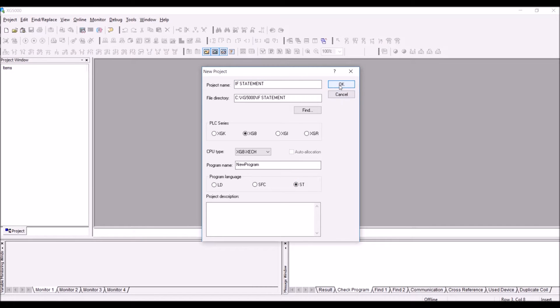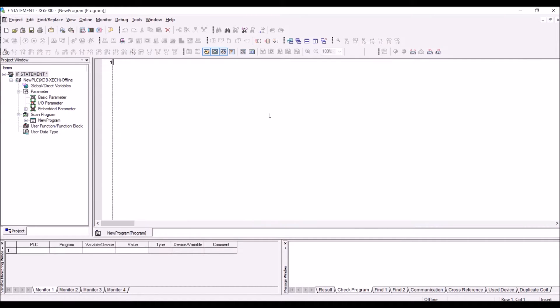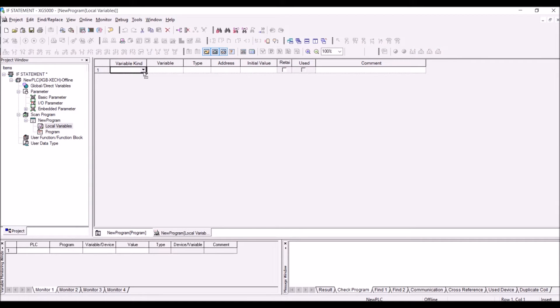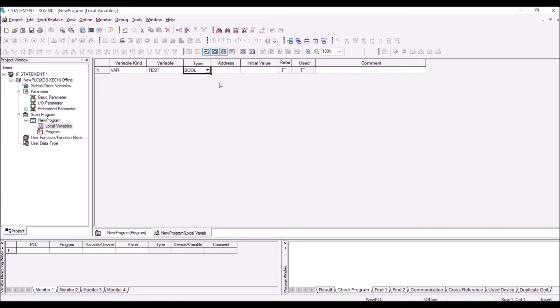This is the program environment. Click on the new program and you have local variables and program. First we will create some local variables, so double click on local variables. Click on the variable kind — it's actually variable type — and add a variable named 'test', type as bool. For the address, you can assign a digital address, for example IX 0.0 for a digital input.